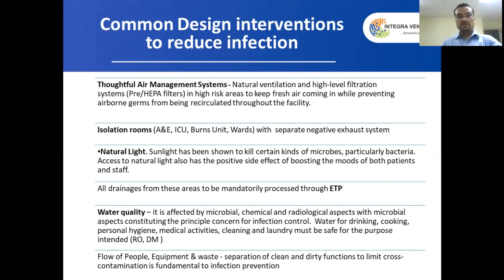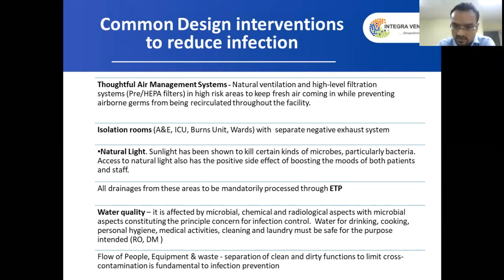This is also becoming mandatory in most places now. The pollution control boards in respective places have made it mandatory that liquid biomedical waste coming out of healthcare facilities needs to be treated before being dispersed into the general drain. So we need to have a proper effluent treatment plant where all the outlets are fed, treated, and then discharged into the general drains.